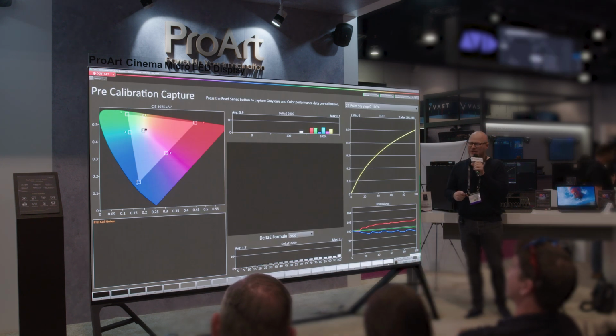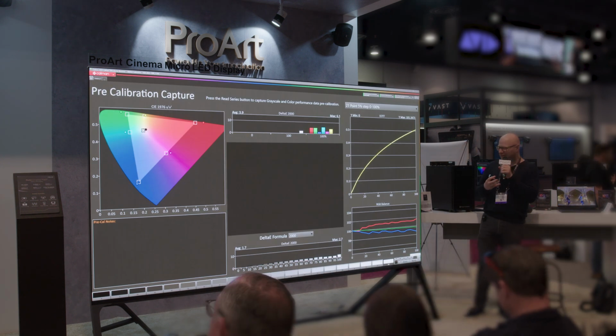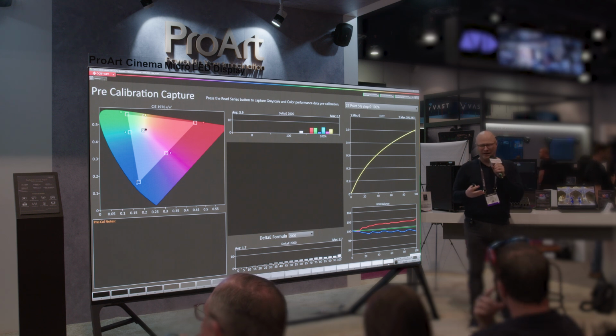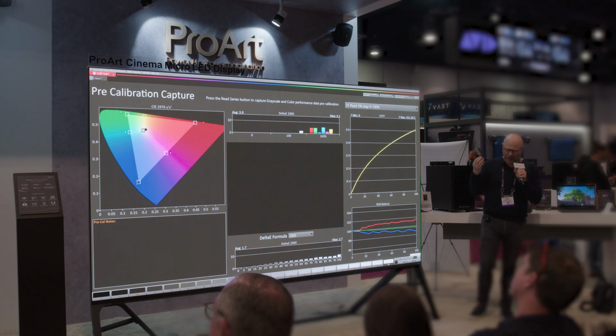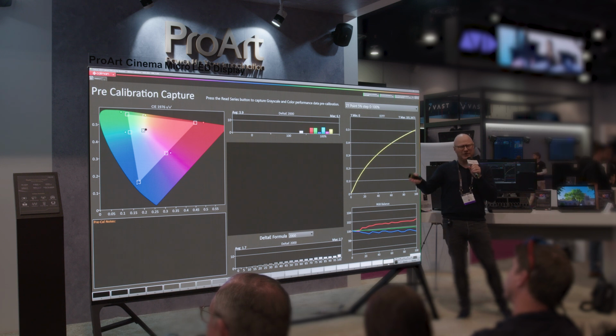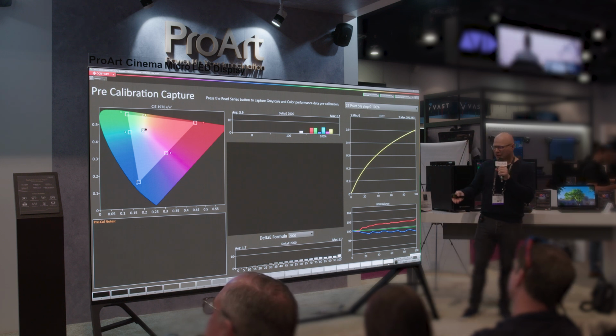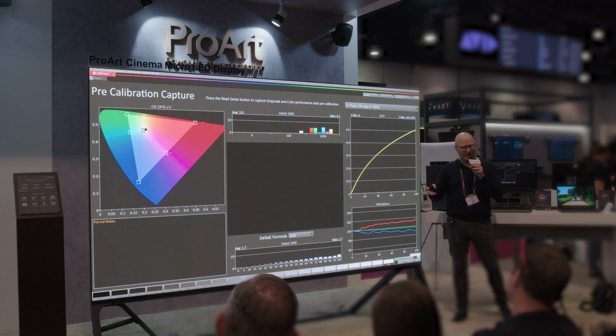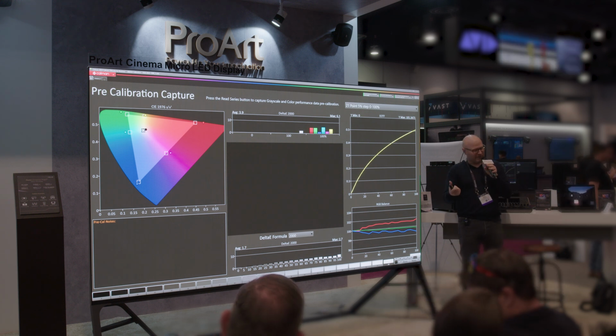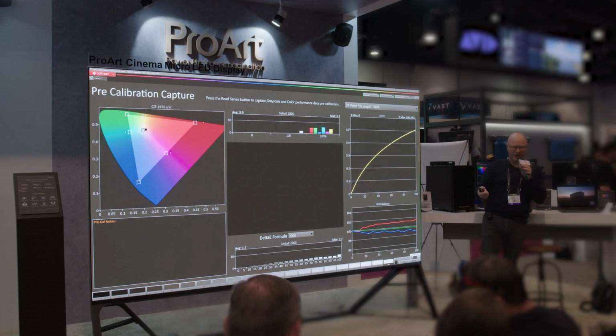We'll do a pre-calibration capture because it's always great to know where the monitor is as you're starting to work with it. Now keep in mind, if you measure a monitor with different meters at different times, you may find some error between them, because the monitor has to warm up, and the meter has to be calibrated properly for the monitor.